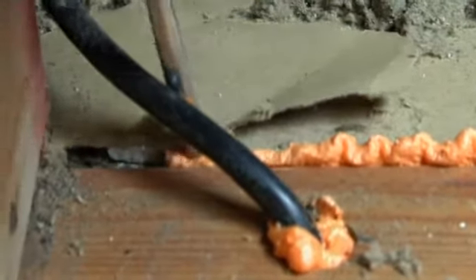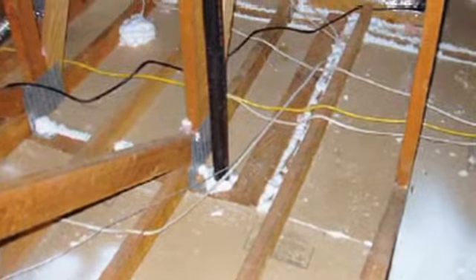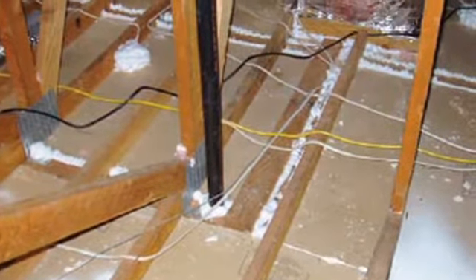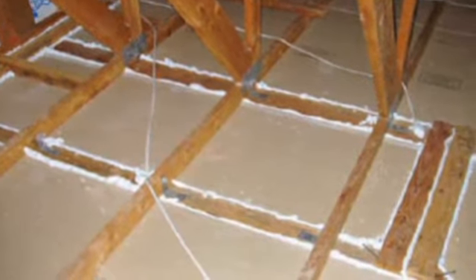When we start our air sealing activities in the attic, we take a blower door reading, seal whatever penetrations we can find, and then take another blower door reading so we can quantify the magnitude of improvement. If we aren't making progress, we look harder for where the actual leaks are. We also use smoke pencils and sometimes smoke generators to actually identify the leakage paths. Our overall goal is to get this plane — the ceiling plane — airtight, separating our conditioned house air from the attic.